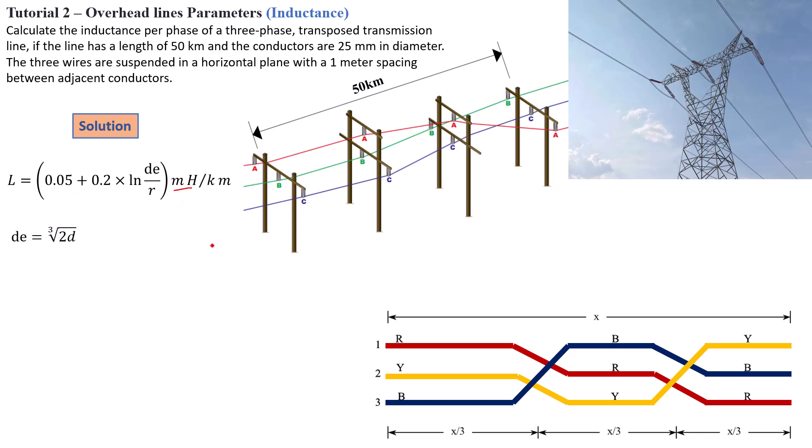So the first parameter here is dE. Now dE is related to the conductors that are suspended in a horizontal plane with 1 meter spacing. If dE is equal to the cubic root of 2d, that basically means your conductors, like in our case, are basically equally spaced. Now if you have a situation where these conductors are actually not equally spaced, which means the distance here is not equal to the distance here, in that case you're going to have dE must be equal to the cubic root of a times b times c.